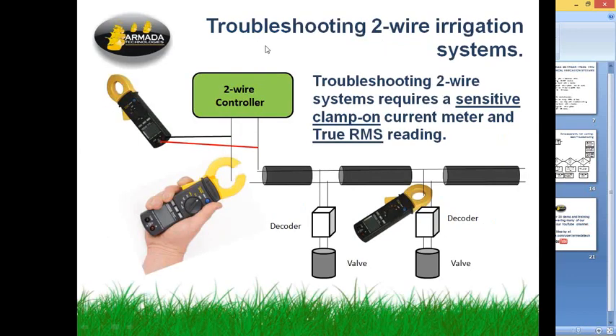So here's just another illustration of the clamp meter in action. You can use the voltage test, as you can see, and you should go to the two-wire controller. Systems vary a little bit, 32 volts, 36 volts, very weird waveforms coming out of two-wire controllers for these systems. So the true RMS meter is very important in that regard. This clamp meter that we sell, the Pro 93, has an RMS voltage measuring function, which is a computing function. Hunter systems have a 1 hertz square wave power feed to the field, which is a very odd thing. Most meters will not read that correctly. You have to have a true RMS meter to read it correctly.